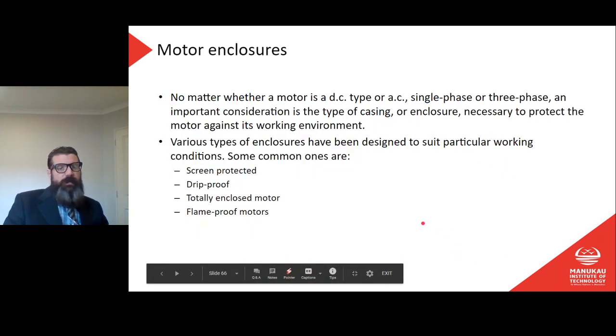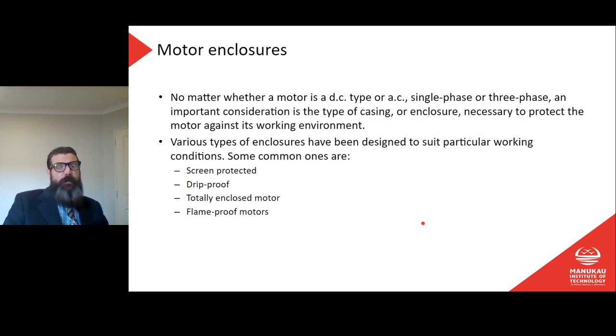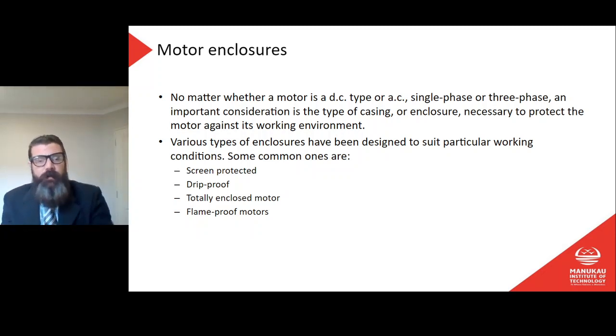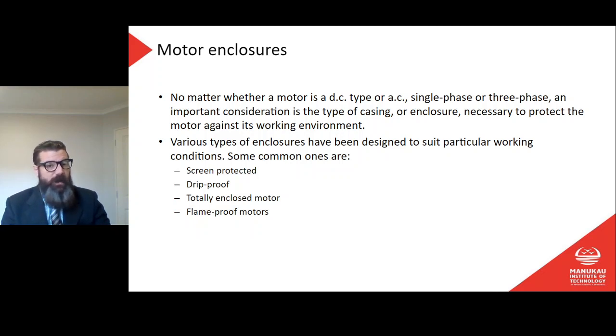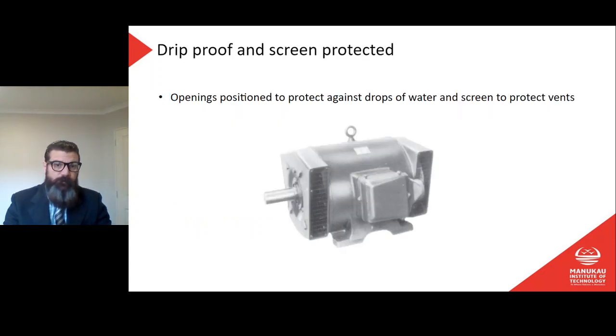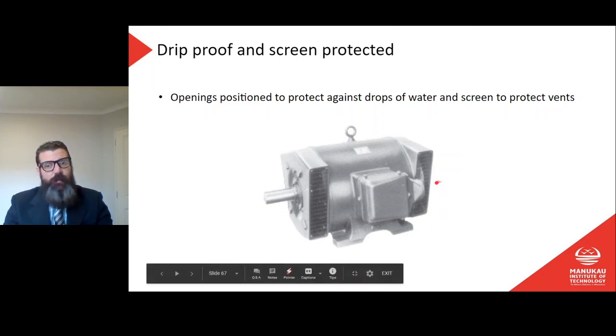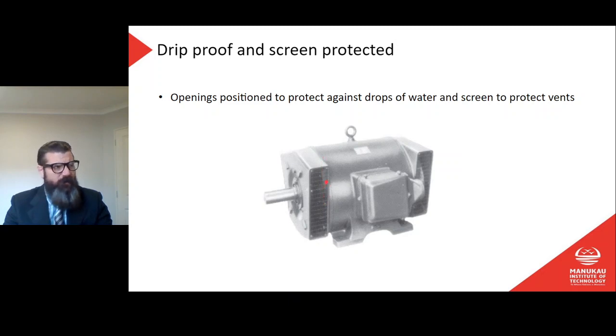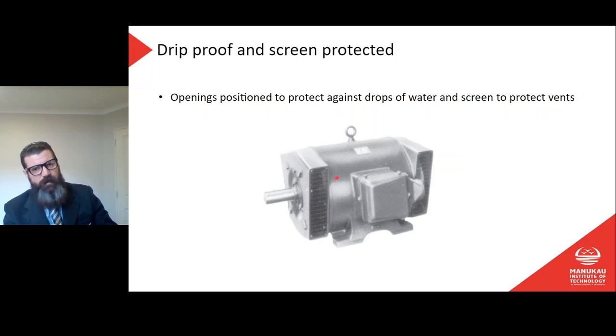An important consideration is the type of casing or enclosure necessary to protect the motor against its working environment. Various enclosure types have been designed to suit particular working conditions. Some common ones are: screen protected, drip proof, totally enclosed, and flame proof. For drip proof and screen protected types, the openings are positioned to protect against drops of water, and screens protect the vents — so no openings face upward, preventing anything from dripping down into the motor.